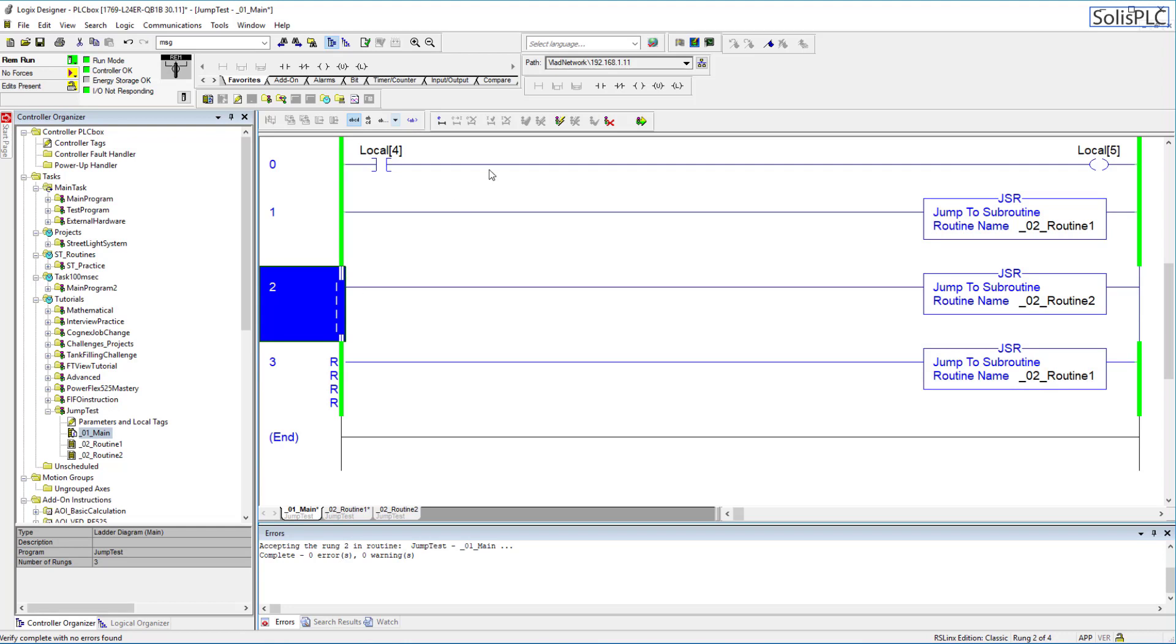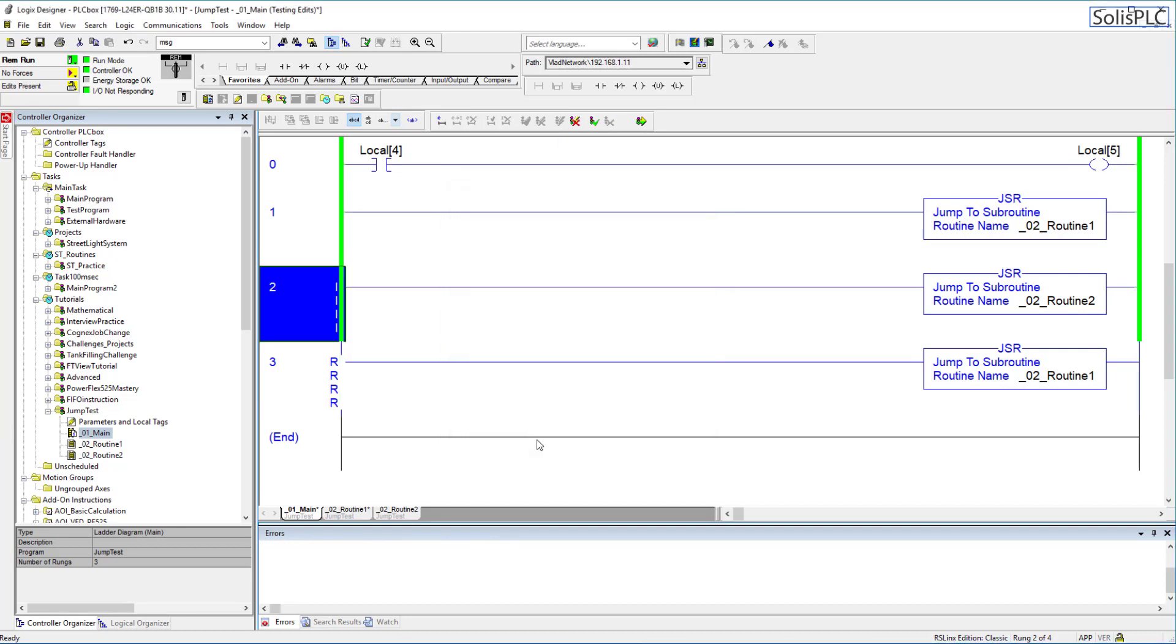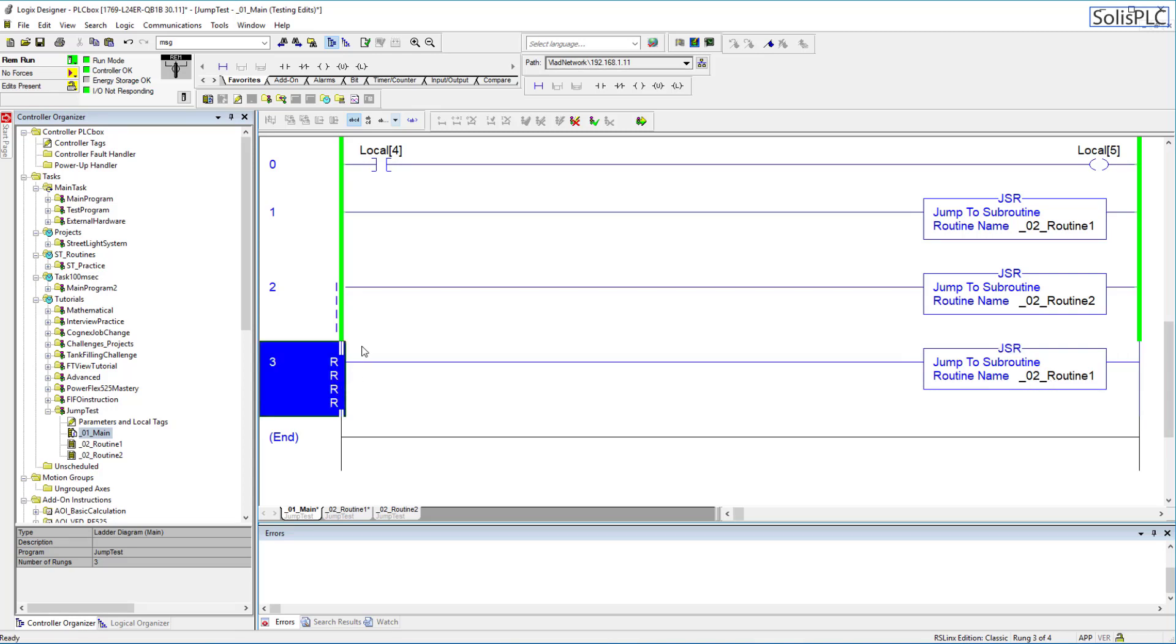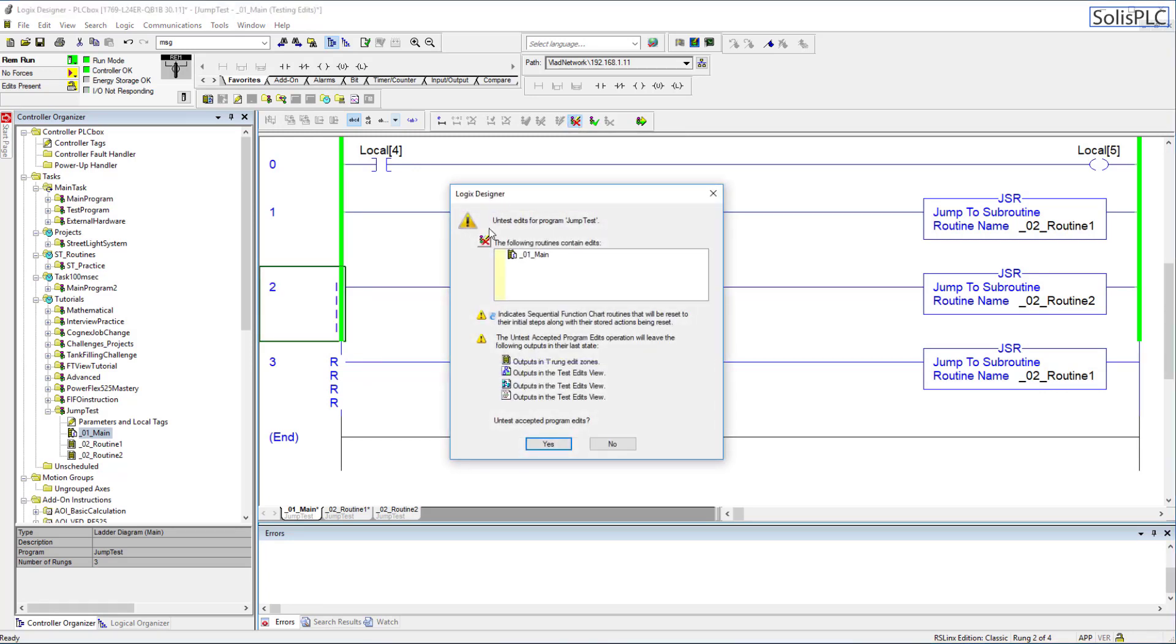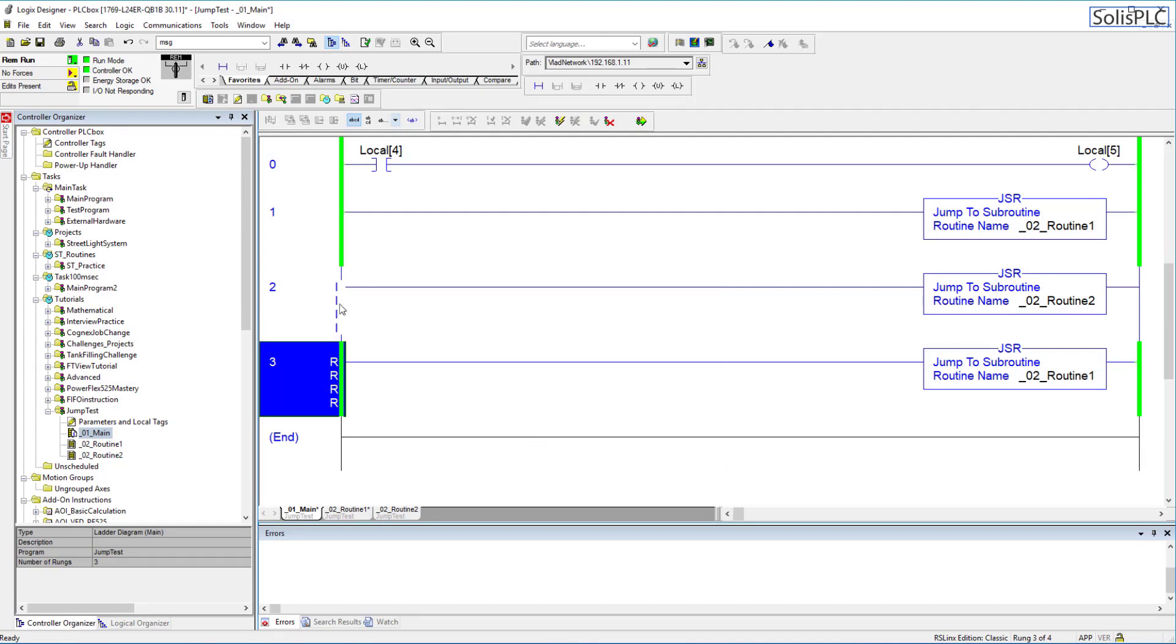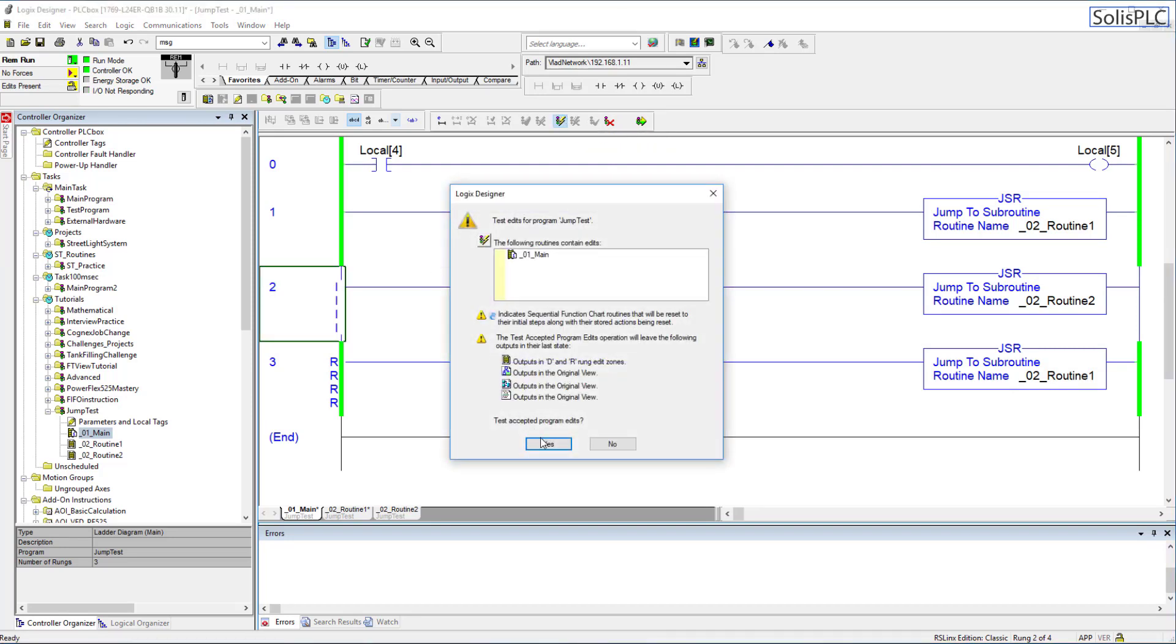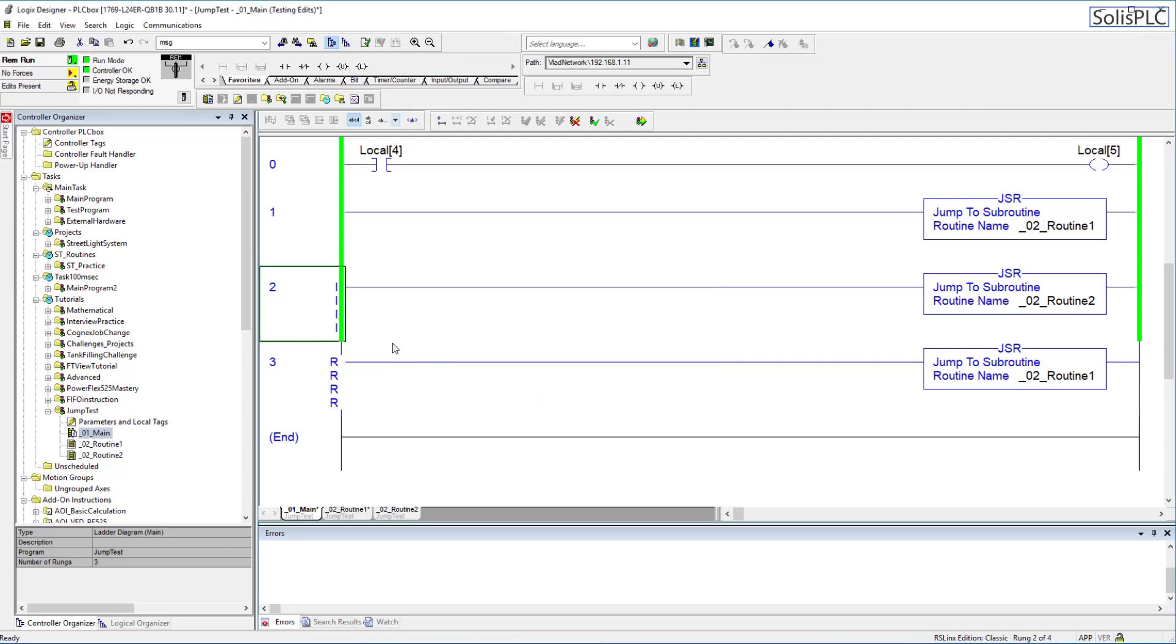So if I test and I click OK at this point you'll notice that the green has switched from this rung to this one which means that at this point I am executing this rung but I still have the previous rung which as you'll notice still calls routine one as a backup. So this is a method where you can test some new pieces of logic and you can at this point let's say for example you have a certain routine that you wrote and you see that it's working as expected then you can accept the program edits and if it's not working you can essentially untest accepted program edits. If you click on untest you'll notice that the rung that's being executed is the old one. So this is essentially a way for you to test a new rung before committing to it completely because once you commit so I'm going to show you this test again and once I commit you'll notice that only one rung is going to stay in place.